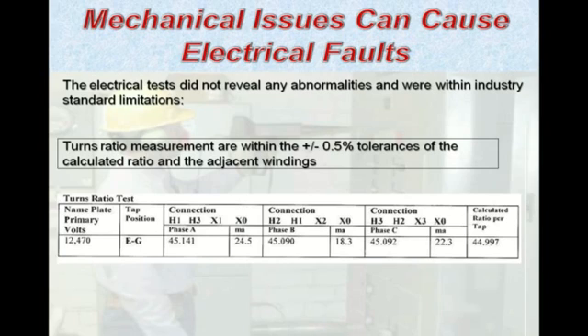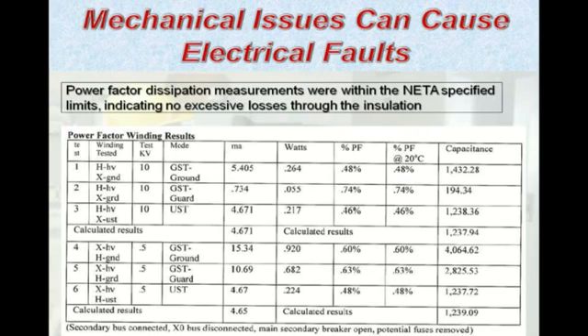The power factor dissipation measurements were within the NETA specified limits, and it does not indicate any type of excessive loss related to watts through the insulation at this point. Now, there are some losses which indicate a marginal degradation. It's not nothing that would be taking the unit out of service or rewinding it at this point, but keep in mind we're trying to be both condition-based and predictive with these units to plan repairs as opposed to allowing it to fail.